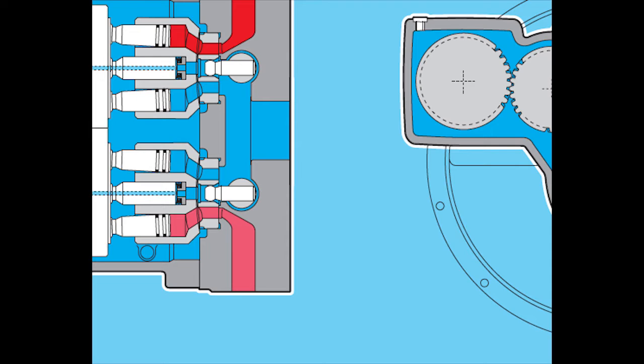Operating Viscosity Range: We recommend that a viscosity, at operating temperature, for optimum efficiency and service life purposes of OPT equals optimum operating viscosity 16 to 36 mm squared per second be chosen. Take in the tank temperature, open circuits, into account.